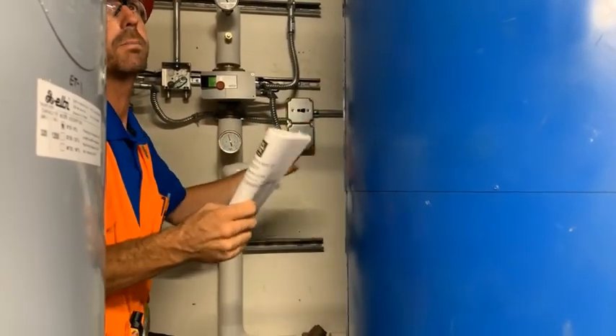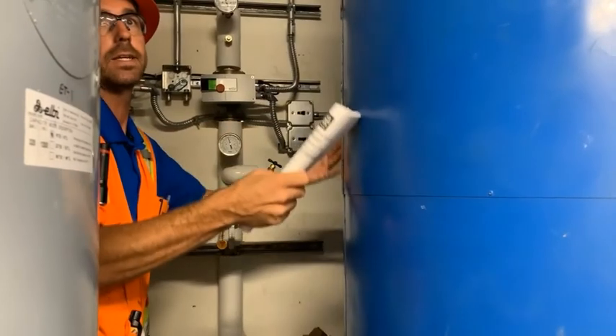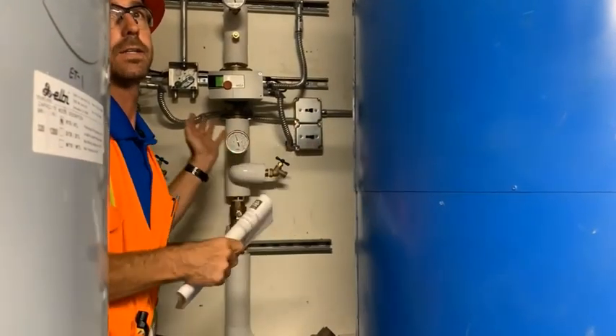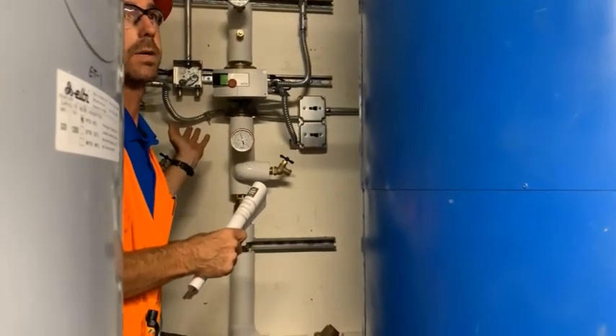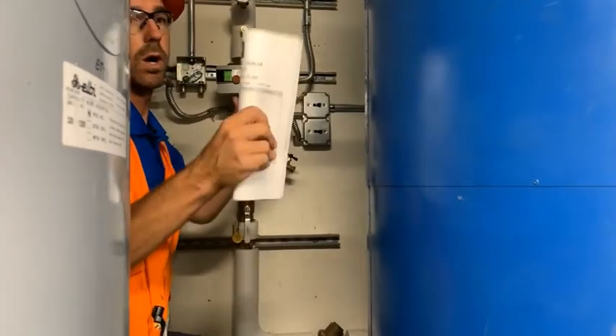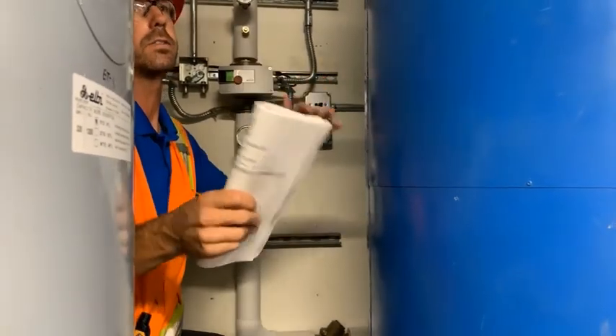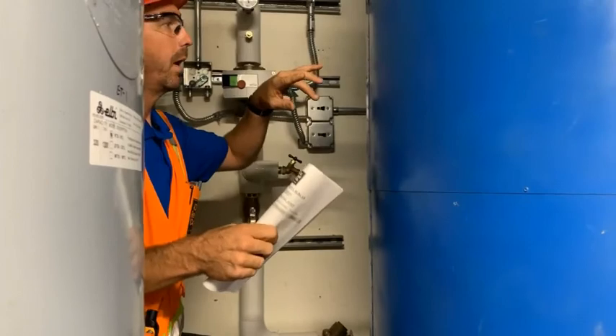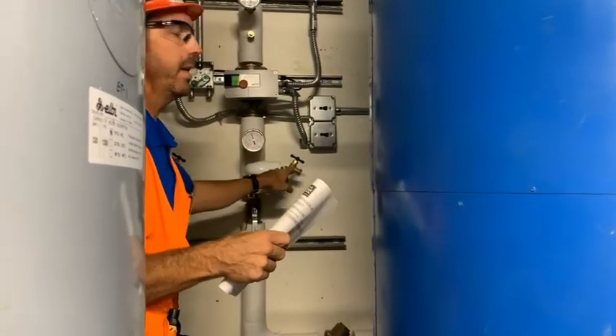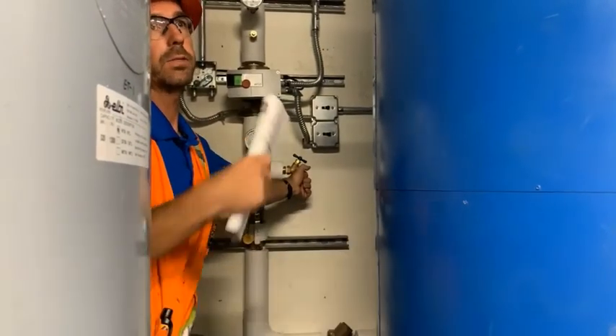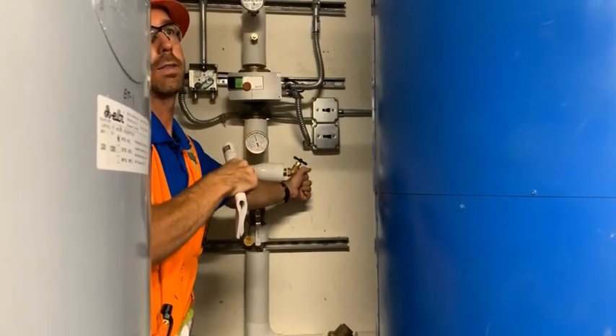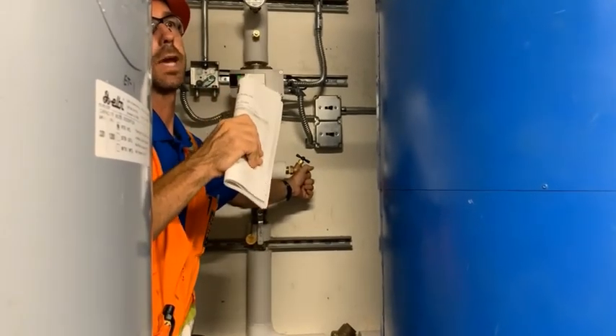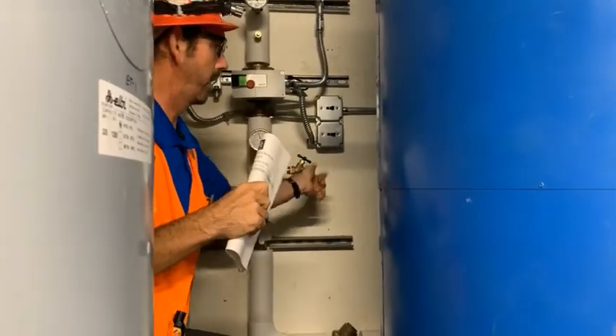Well, if it's an emergency, shut valves and isolate it that way, but you can't forget to shut off these pumps, okay? Because they will burn up. So if you do your work on the hot water, whatever floor it is, it's all tied together. Make sure you come in here and shut these valves again and hook up a hose, and this will help you bleed the air that gets stuck at the top of the hot water system, okay? You'll force it down. Just hook up a hose, put it into a drain.